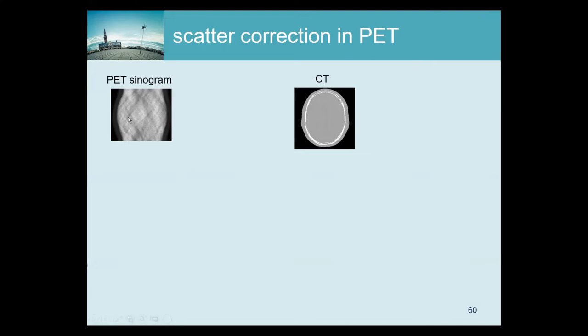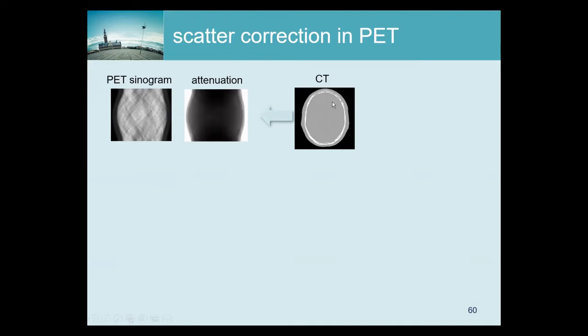That's illustrated here. So we have a PET sinogram, and these days you almost always have a CT because if you buy a PET scanner, it normally comes with a CT. So that means this is the input we have, and now we want to make a scatter-corrected reconstruction. The first thing we do is compute an attenuation sinogram from the CT, and for that we have to convert the CT image to attenuation at 511 keV.